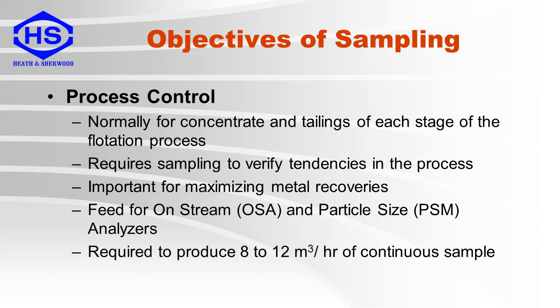These are the properties of process control samplers. They are normally for concentrate and tailings of each stage of the flotation process. They require sampling to verify tendencies in the process and are important for maximizing metal recoveries. They are used to supply a sample to an on-stream X-ray analyzer or a particle size analyzer, and are required to produce 8 to 12 cubic meters per hour of continuous sample.